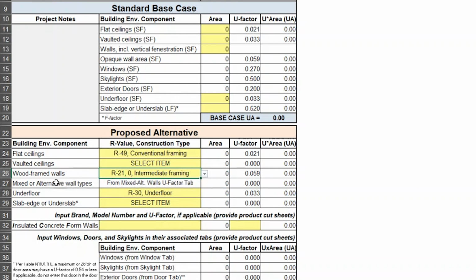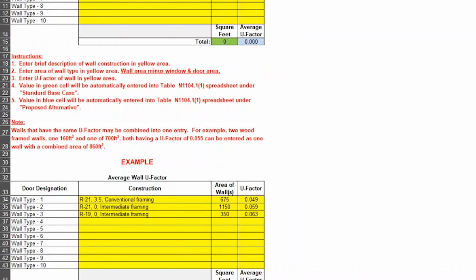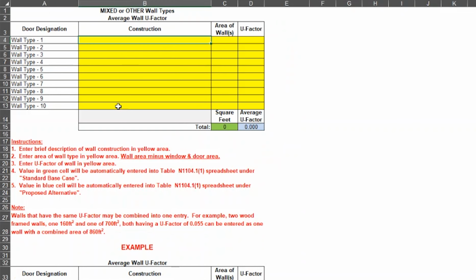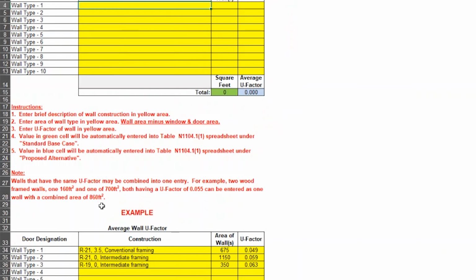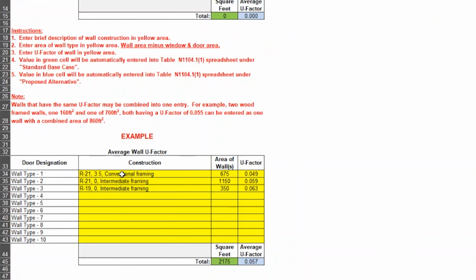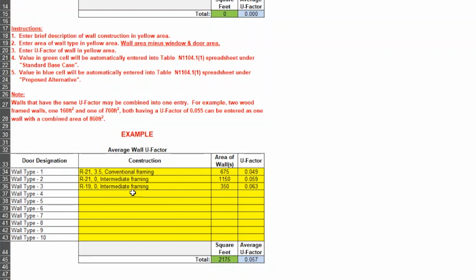If you have a wall that isn't in there, we have mixed or alternate frame types, the U factor tab, where you would go to this tab and put in the actual wall values, including on every one of these, we have an example wall type showing how these things would be input. You have the square foot of area and then the U factor for those specific wall types. You may have things like insulated concrete form walls. You may have other types of mass walls or CLT walls. The customer would put in the area of the walls and the U factor for those.